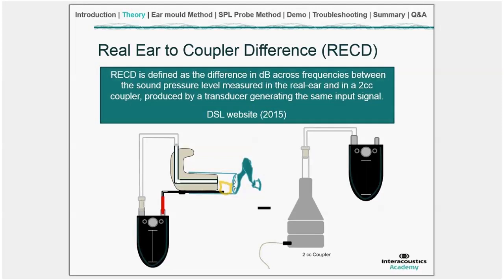An RECD measurement takes two measurements: the real ear response and the coupler response. We place a probe tube in the ear to measure the sound pressure level at the eardrum while the ear is occluded with an ear mould. Then we measure the characteristics of the 2cc coupler using the same stimulus at the coupler microphone. Subtracting these two measurements gives the coupler the characteristics of the ear canal.